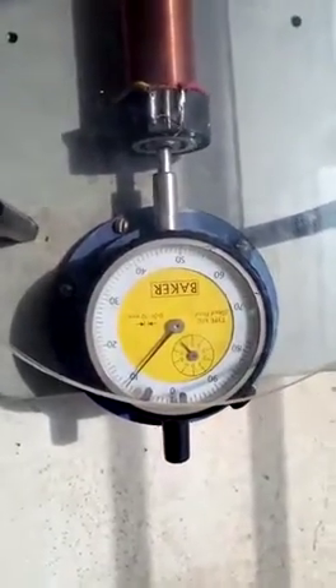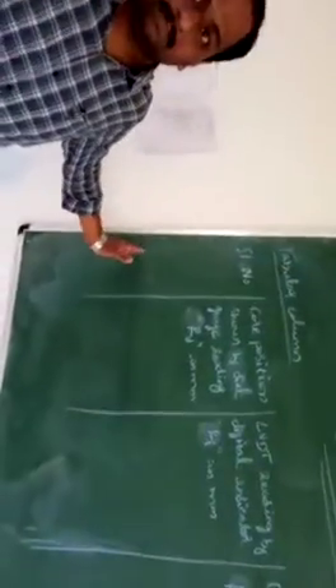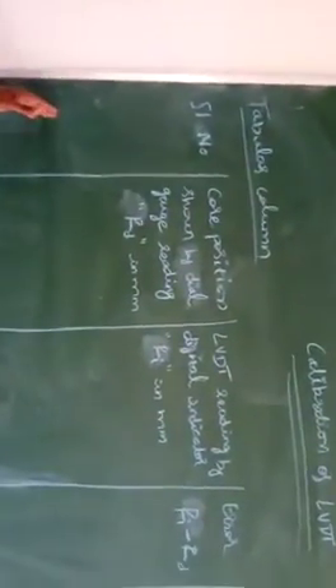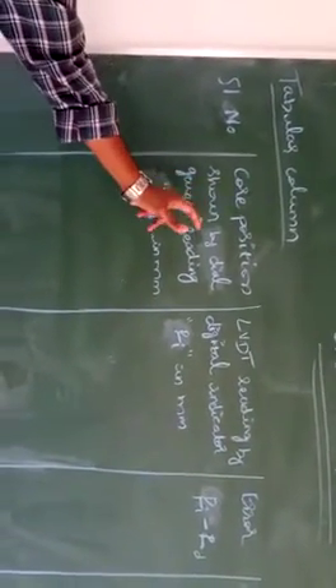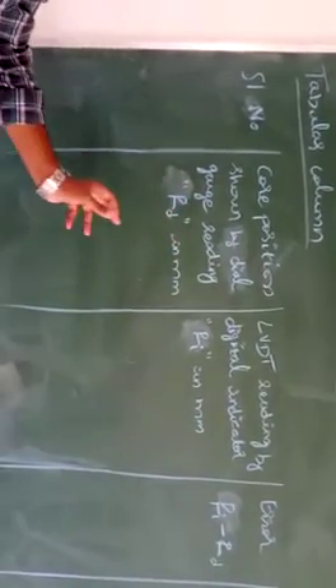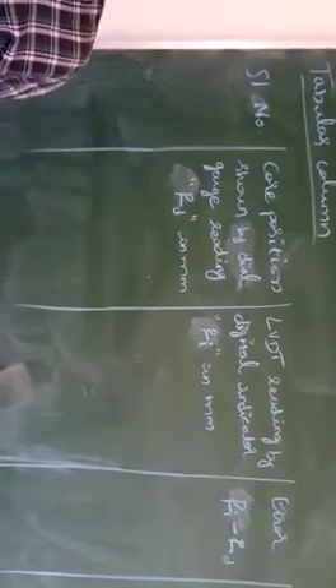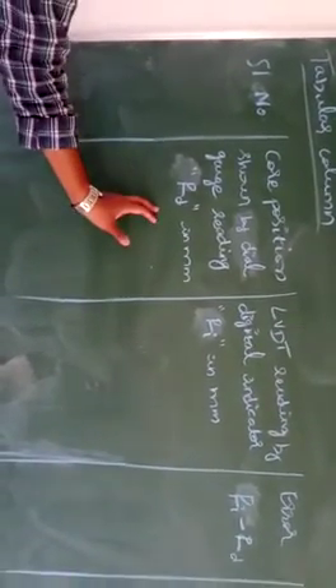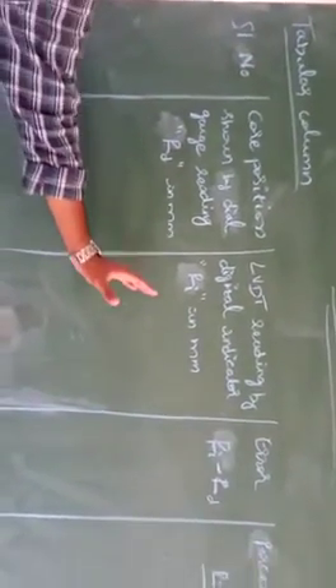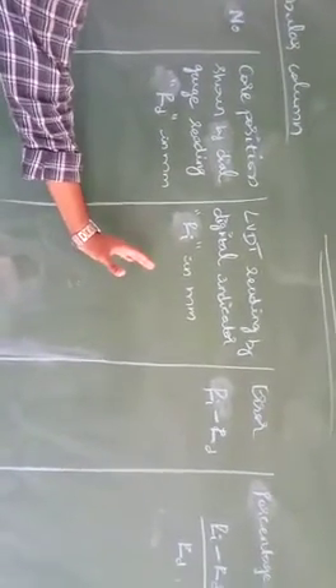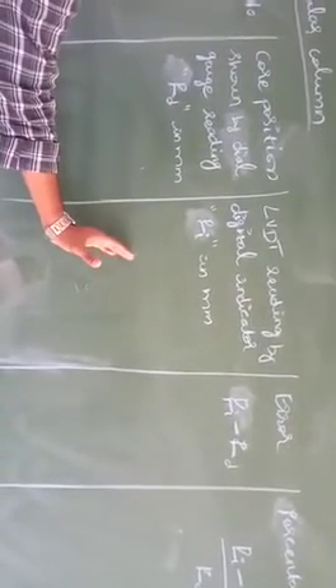Now we shall see the calculation part for the calibration of LVDT. That is the serial number, that is the number of readings. Next is the core position shown by dial gauge reading. That is what the dial indicator or the dial gauge is showing, you are going to note here. And then the LVDT reading, which is shown by the digital indicator, you are going to note down here.